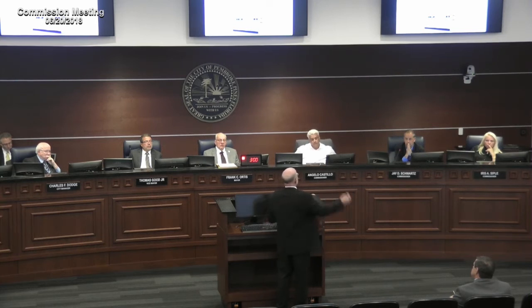They send a guy out with a truck down the street, he pulls in, and if there's no power, he starts the generator and it's back online. He's manually disconnected it from FPL, awaiting the electricity to come back online. Then when it does, he disconnects it manually. This building just did that automatically—perhaps the IT was a little slow, but that automatic sense is what we want at the water well field.